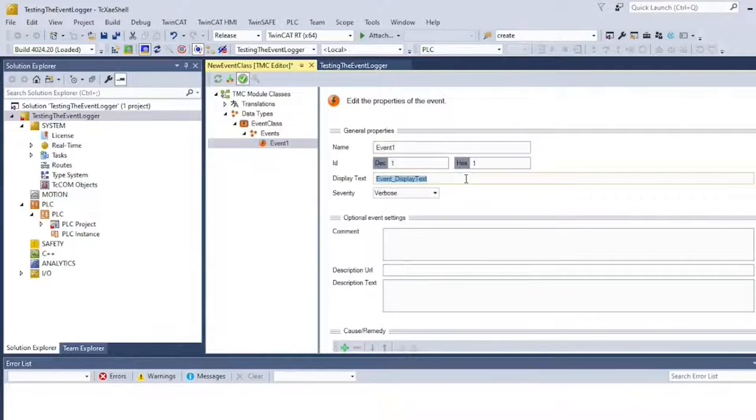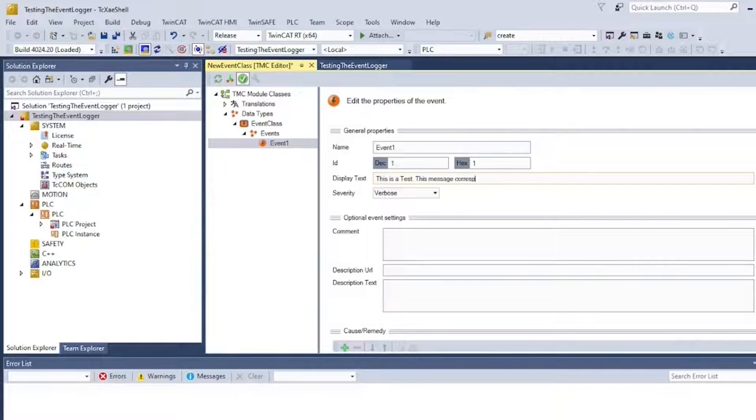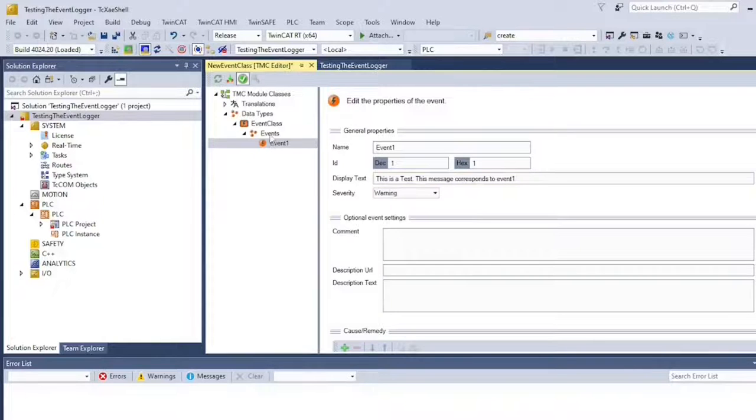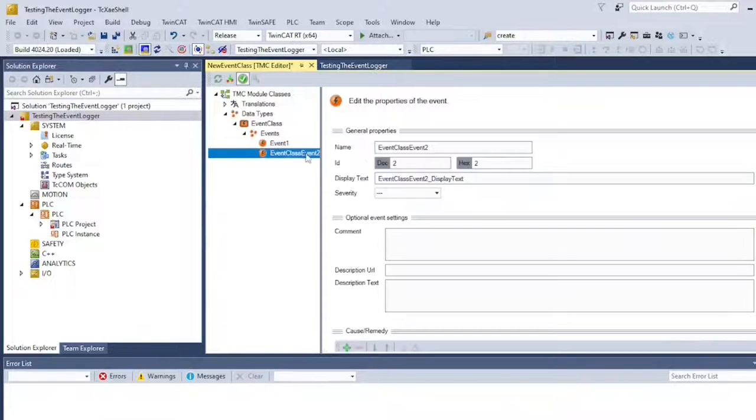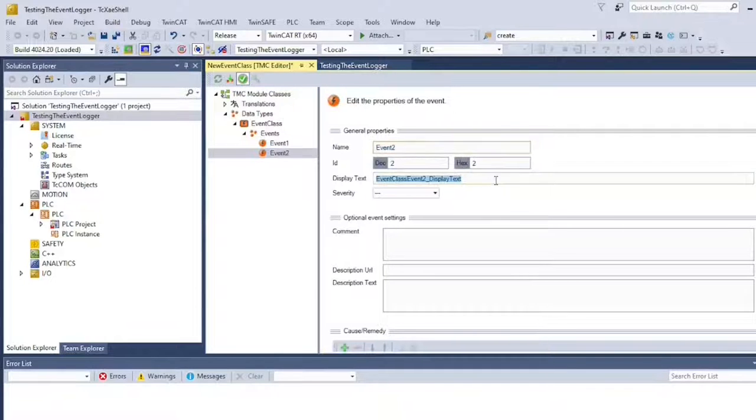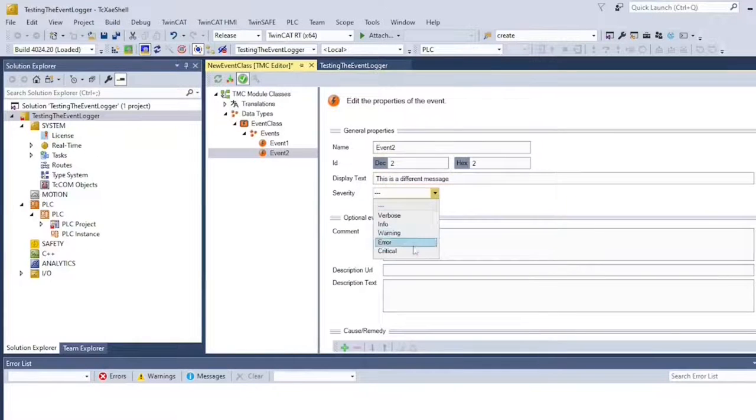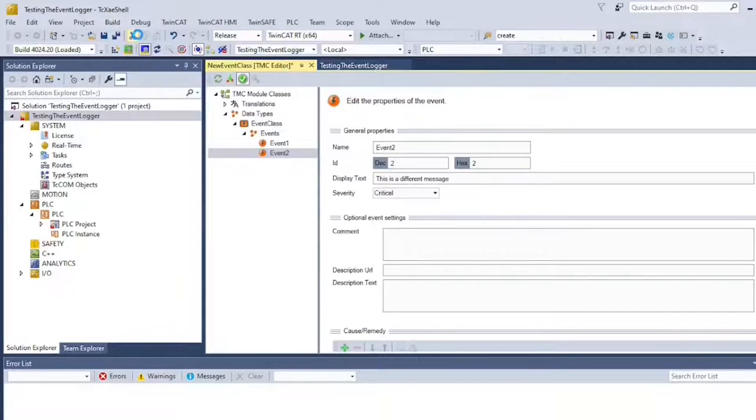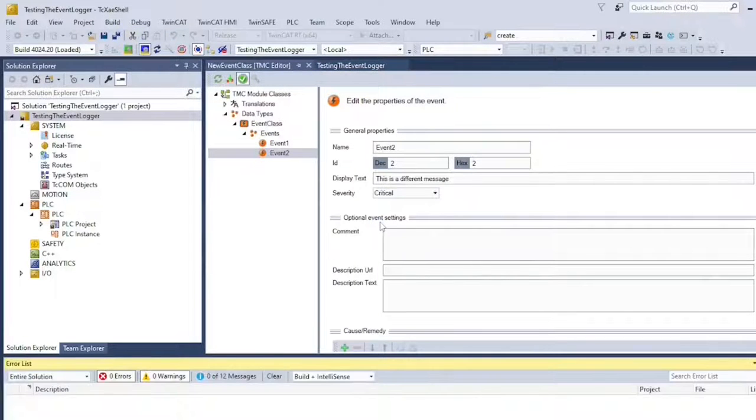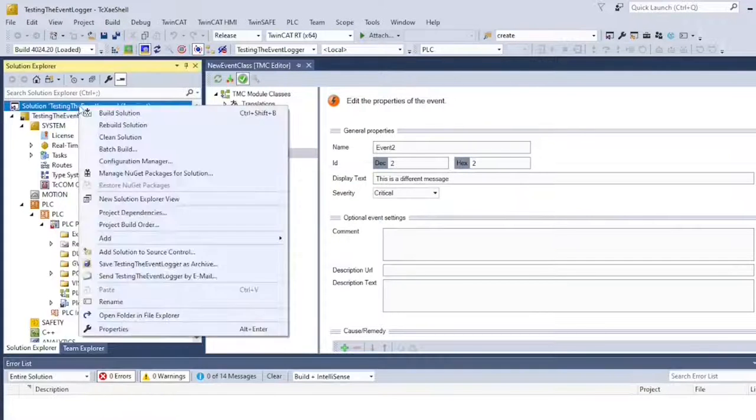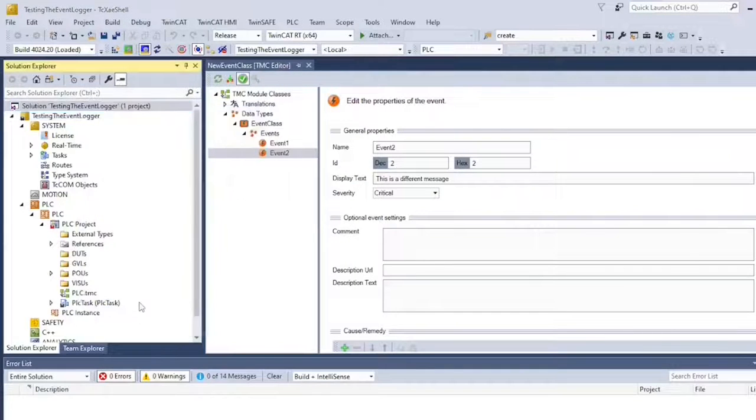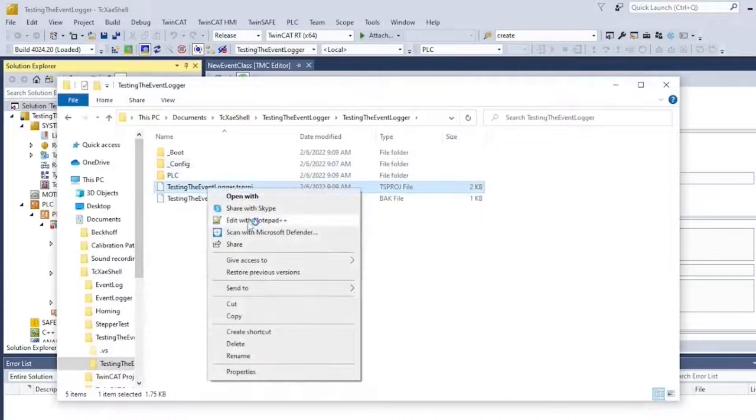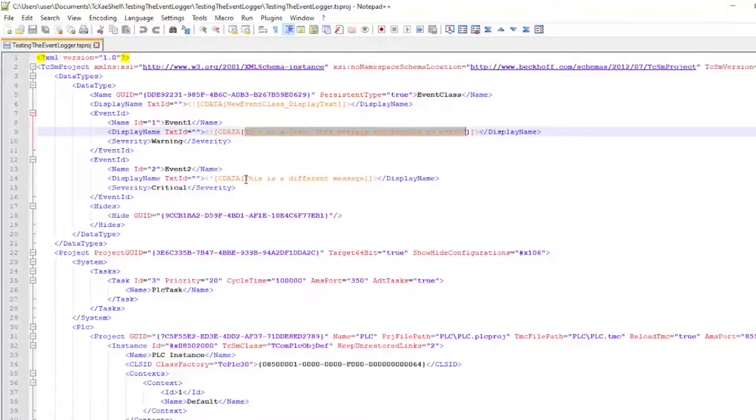So we're going to call it Event Class and it comes with one event. We're going to change it to Event 1 and add a display text to it. I can also set the severity. It's going to be a warning and I'm going to add a second event. This is my event number two. Same thing, you're going to add a text and a severity level. This one's going to be critical. Once I have it, I need to rebuild my solution. This will update my tsproj file and include these events and this event class in the project. So now if I navigate to my folder and open up the tsproj file, I can see that the event class and the events I created are now listed here.